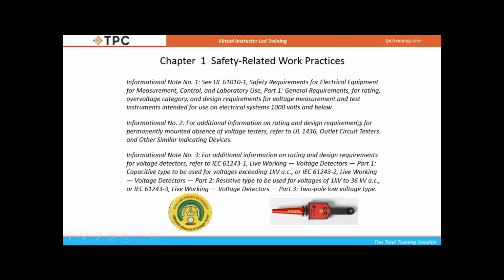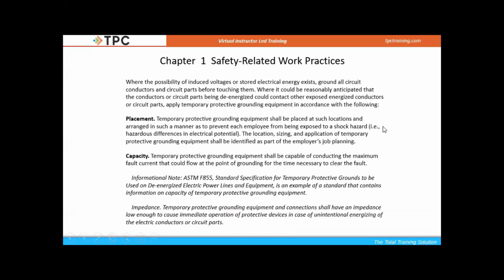I do want to mention that they do make a contact tester for voltages above 1,000 volts. It might not be as accurate as we like it, but I can tell you this, if I put it on 7,200, depending on how my connection is being made, how much pressure I'm putting on it, I might get 7,000, but at least I would know that there's a voltage there. But if there is no voltage, it would definitely say zero. So I could either use a contact or non-contact tester when I got above that 1,000 volts.